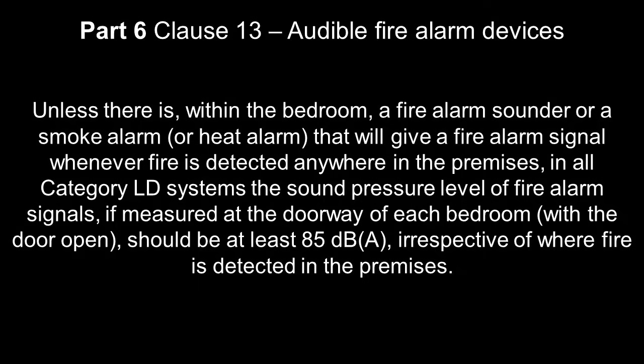So, yeah, what we're saying is that unless there is within the bedroom a fire alarm sounder or smoke alarm or heat alarm that will give a fire alarm signal whenever fire is detected anywhere in a premises, so not just locally but anywhere. This is why you need to interlink your alarms. In all category LD systems, the sound pressure level of a fire alarm signal, if measured at the doorway of each bedroom with the door open, should be at least 85 dB, irrespective of where the fire is detected in a premises. So what we're saying is, if there's a fire in the kitchen, we need 85 dB at the bedroom door. Do you need to measure that, Simon?